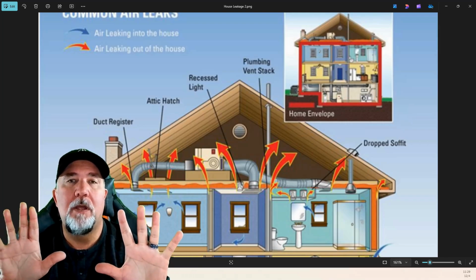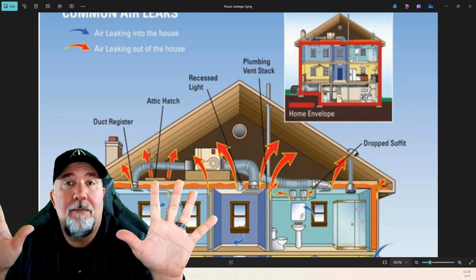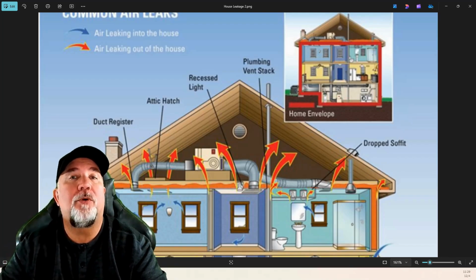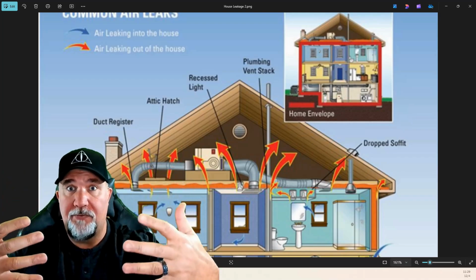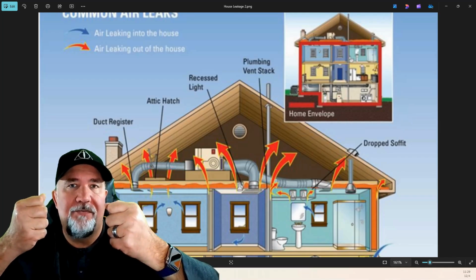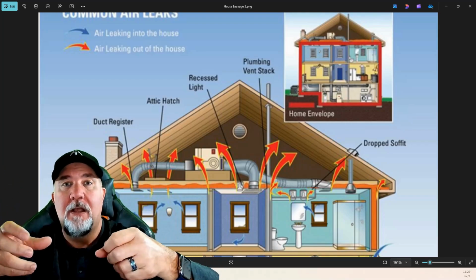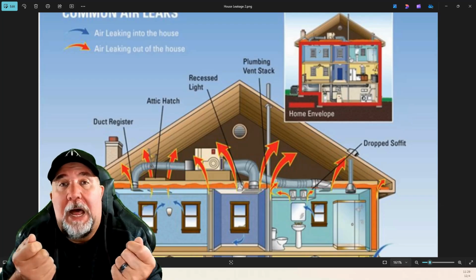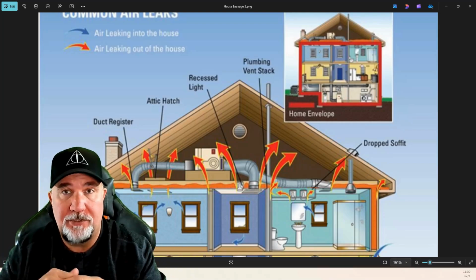Just like you and I, there's a point in time where if I need to push something, the item becomes too heavy and I can no longer push it. It's reached my max. Same thing with pulling. There comes a point where the weight gets too much and I am no longer able to pull it. Same thing with air handlers. If I have a filter and I'm pulling air through that filter, but the filter gets too clogged or it's too thick, I can then start to restrict how much air I can pull through that, up to and including not being able to pull anything, and you could cause motor failures, you could cause all kinds of other issues.